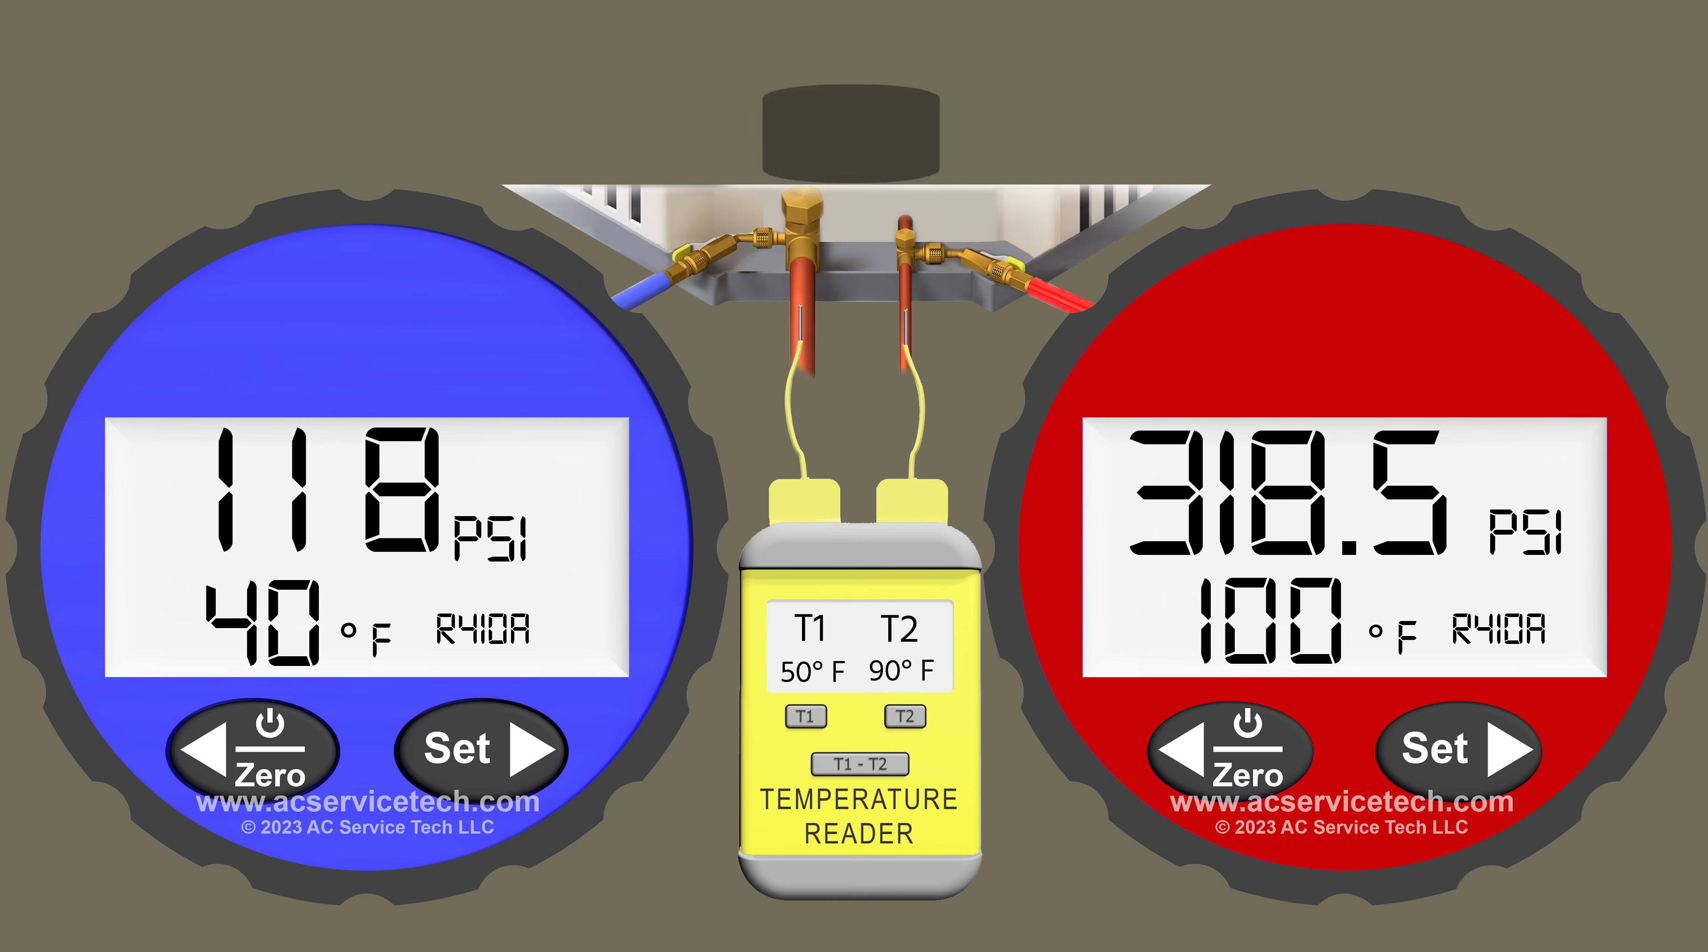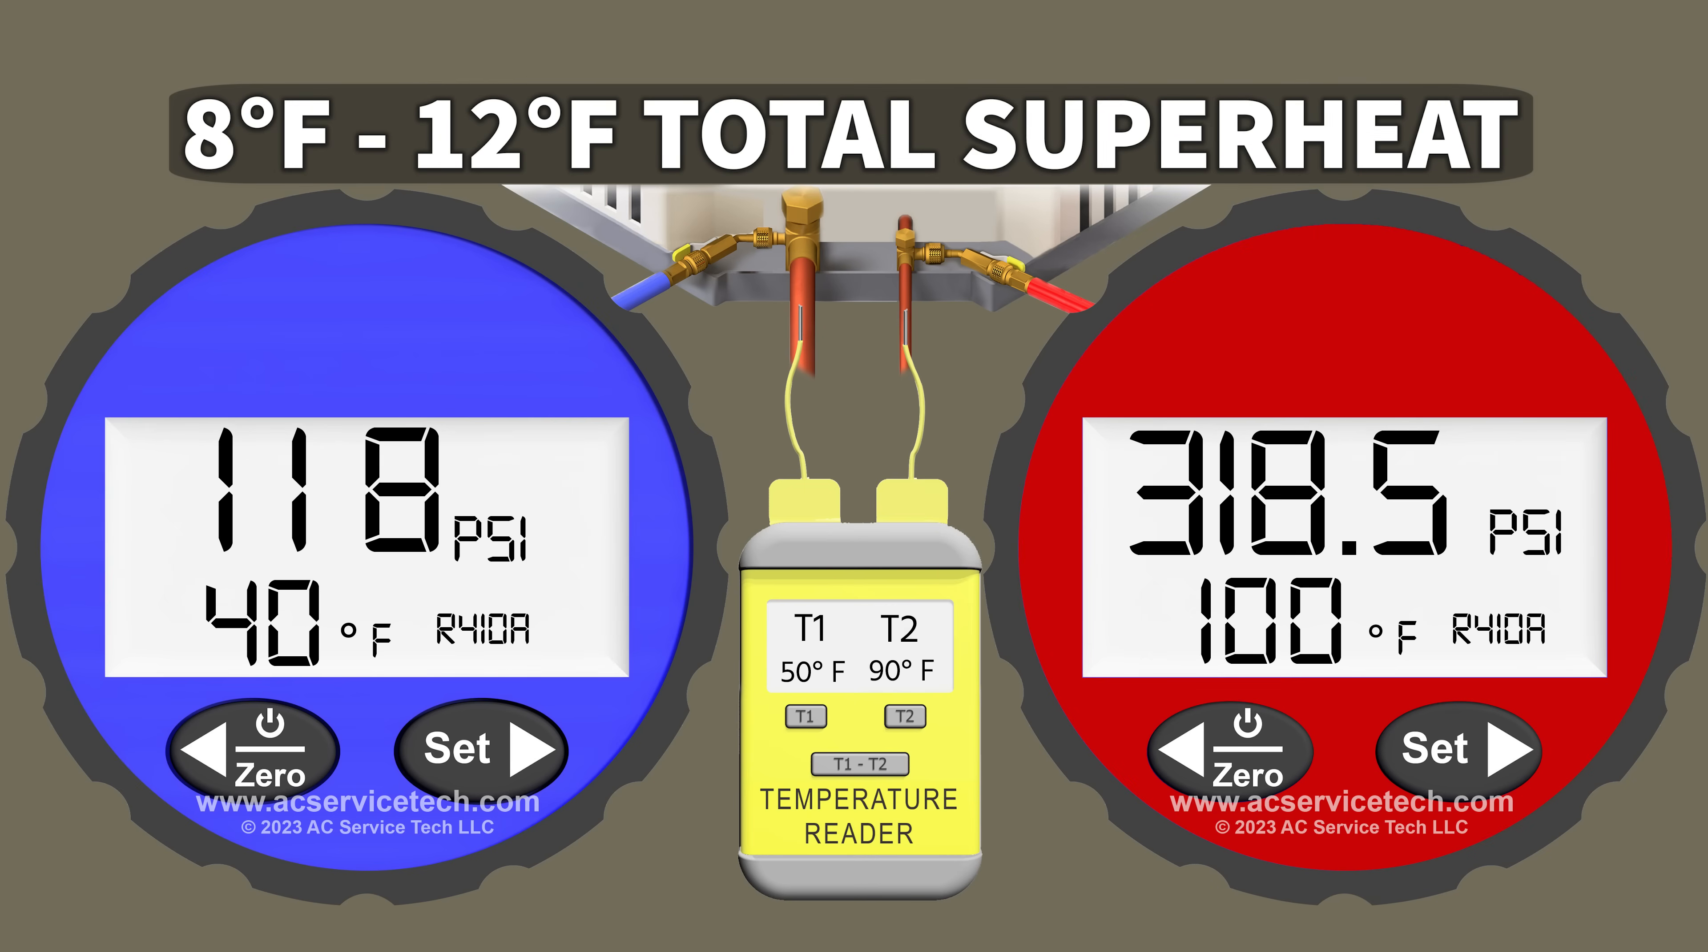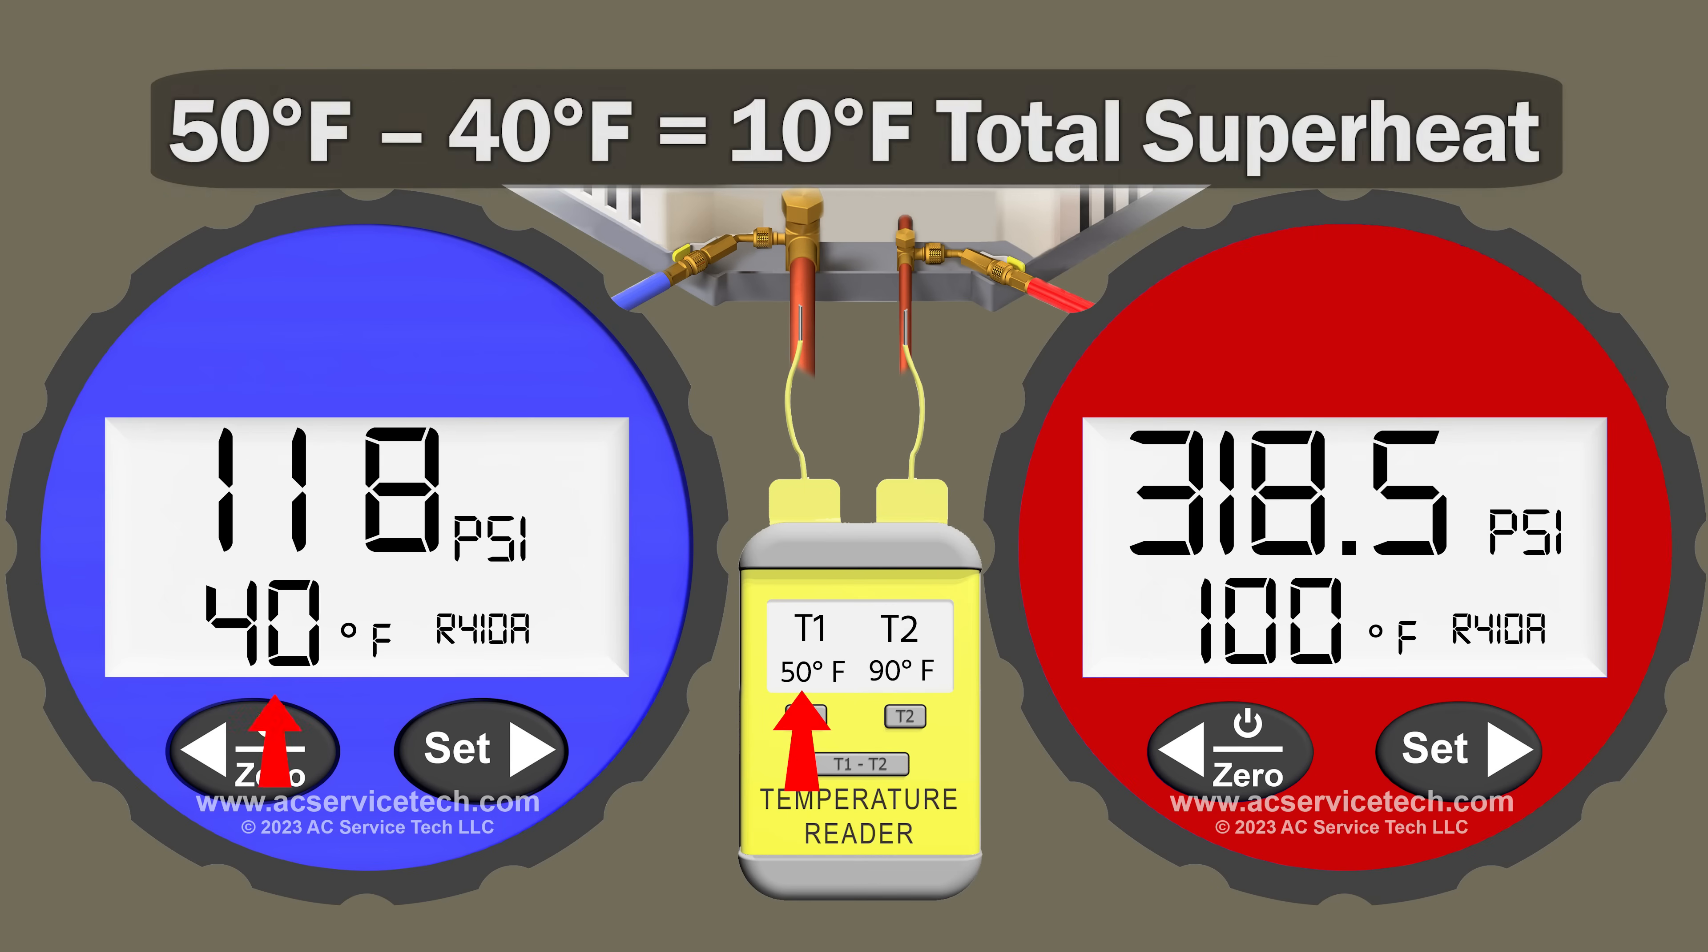Then you will go ahead and measure your superheat. You should have anywhere between 8 to 12 degrees, but really maybe 7 to 14 degrees is still okay, as your total superheat measured on your large vapor line at the outdoor unit.